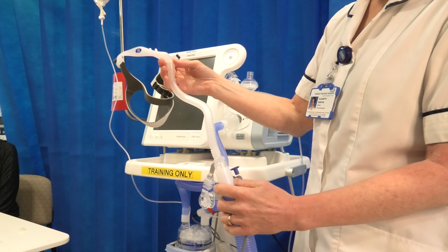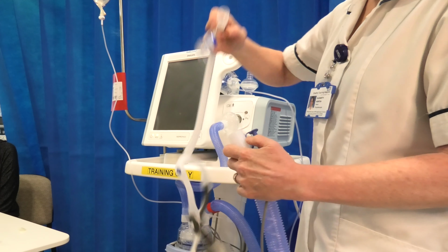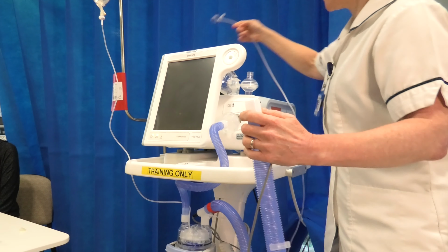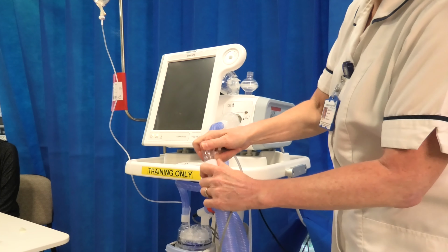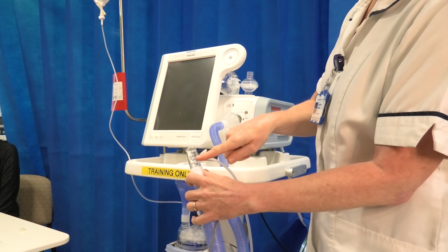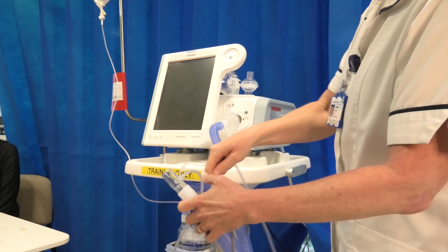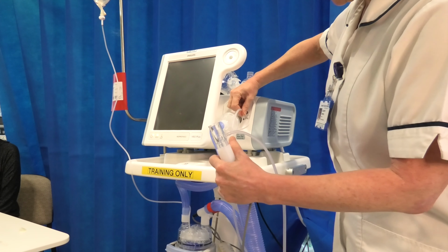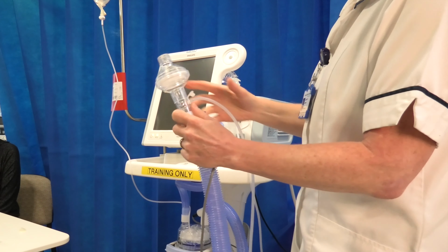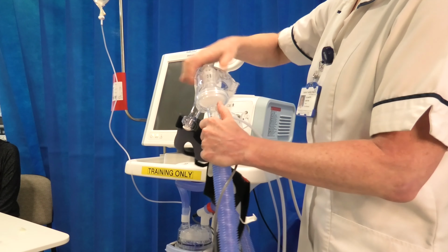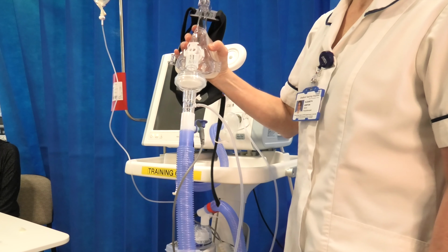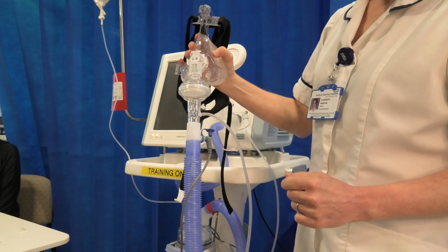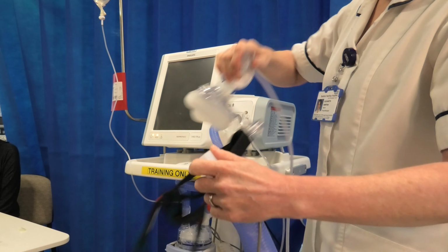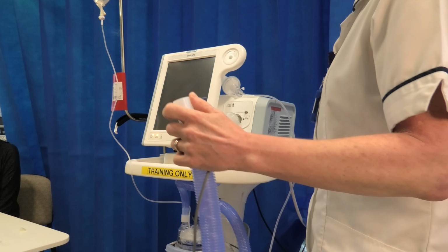If I wanted to use this wet circuit for CPAP, then I would take out my nasal high flow cannula. I would need an exhalation port, which comes in the wet circuit bag. You can see there's a hole there for the patient to breathe out. I would need to attach my pressure line onto the ventilator. I would need a filter, and then attach my CPAP mask, and I'm away to go. If I wanted to change that back to nasal high flow, all I would have to do is take that whole piece out, disconnect my pressure line, and put my nasal cannula back in.